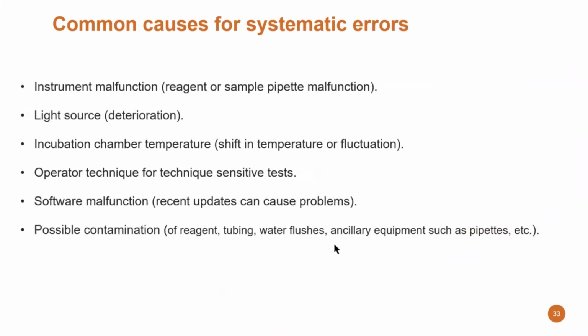Instrument malfunction, reagent or sample pipetting malfunction could be an issue for systematic errors. The light source, or the incubation chamber temperature, may have shifted. Operator technique or a technique sensitive test, software malfunction. There might be recent updates which may be a reason for causing a problem, and possible contamination of the reagent, the tubing, the water flushes, and ancillary equipment such as pipettes, and so on.